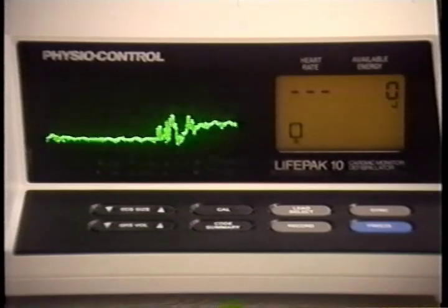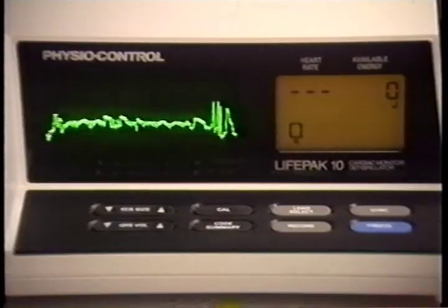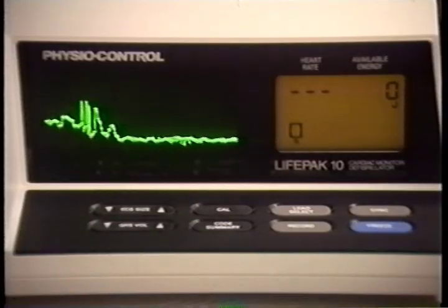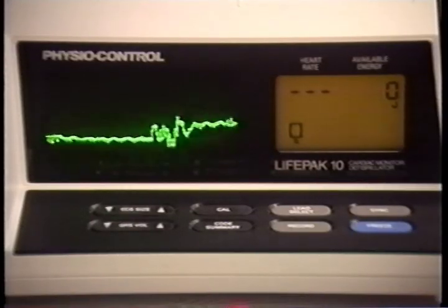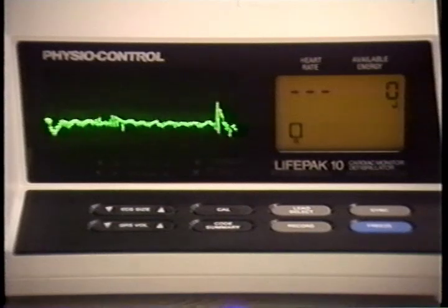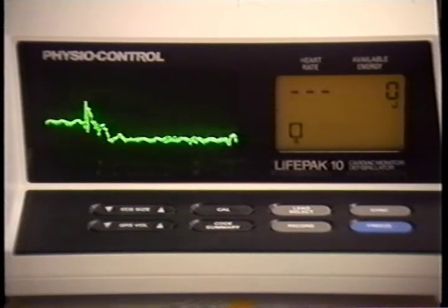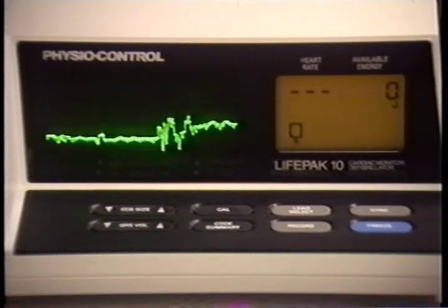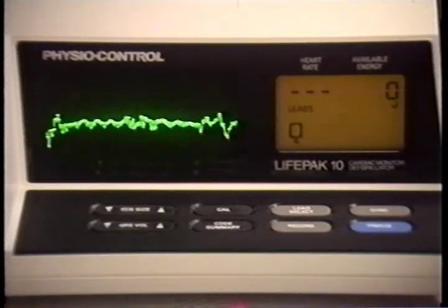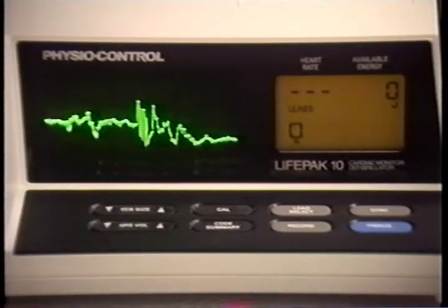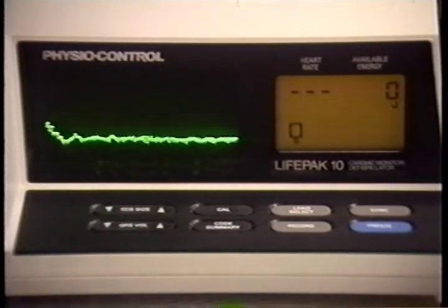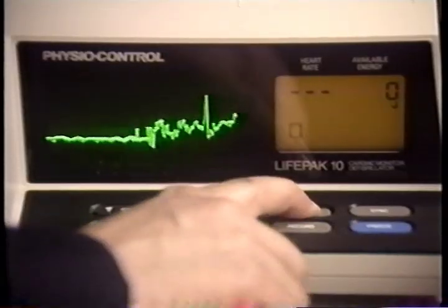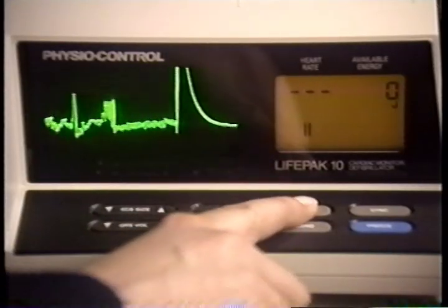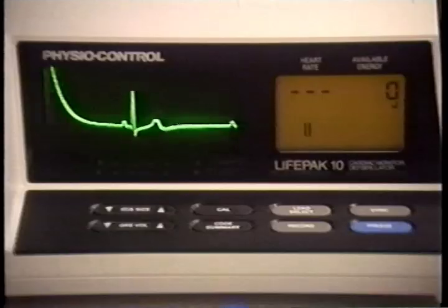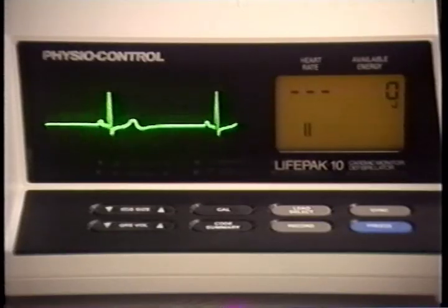To begin pacing, connect the 3-lead patient cable and select lead 1, 2, or 3. You cannot pace while in the paddles mode. If you try to do so, a leads message will appear on the status display accompanied by 3 tones. If this occurs, connect the patient cable and select a lead. A leads message can also appear if the pacing cable is not connected to the pacing electrodes, or if the pacing electrodes are not attached to the patient.